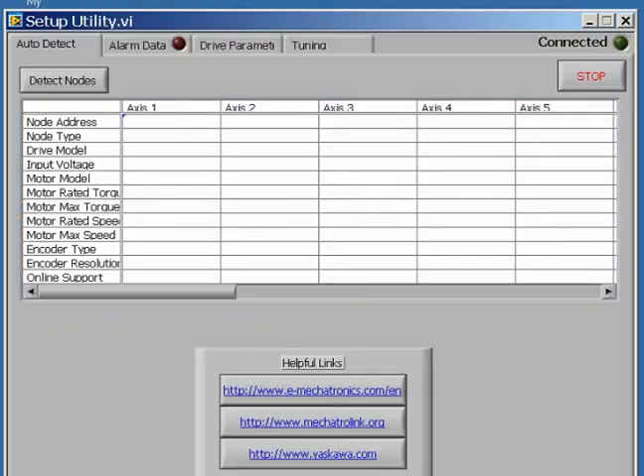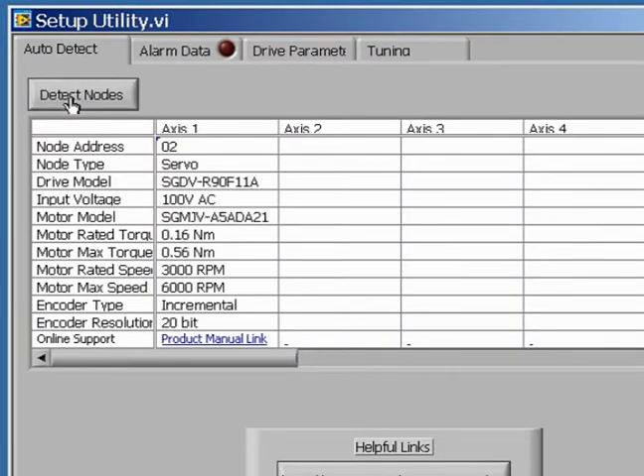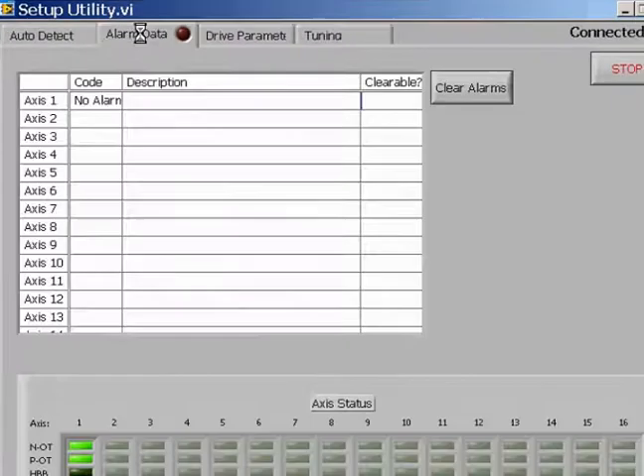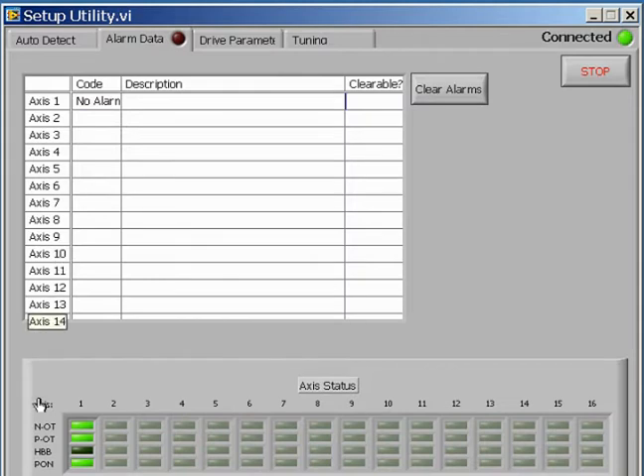Start the setup utility. Click the Detect Nodes button. The utility will search for MechaTrolink devices. Once found, any alarm status will appear in the Alarm Data tab. We notice that there is no alarm, but there are three status bits that are illuminated.